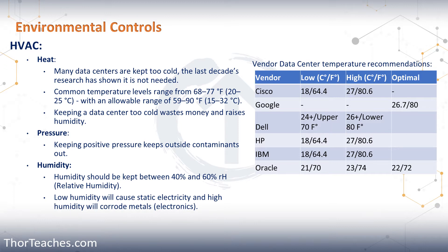Those are the optimal ranges, but they also have allowable ranges — where the equipment is going to keep functioning, but it is not super good for the equipment. They will deteriorate faster and not work optimally. Those ranges are between 59 and 90 degrees Fahrenheit, or 15 to 32 Celsius.